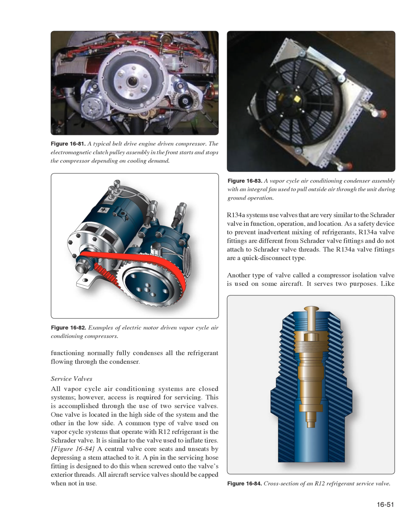The compressor, depending on cooling demand, functioning normally, fully condenses all the refrigerant flowing through the condenser. Service valves. All vapor cycle air conditioning systems are closed systems; however, access is required for servicing. This is accomplished through the use of two service valves. One valve is located in the high side of the system and the other in the low side.